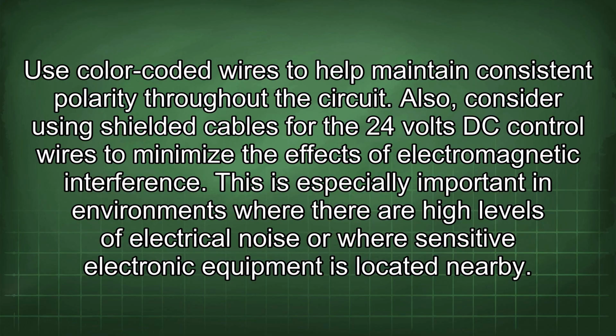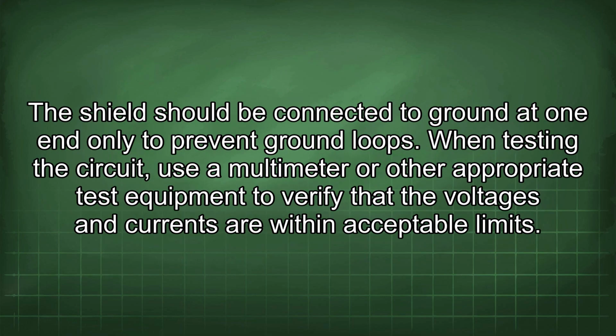Also, consider using shielded cables for the 24 volts DC control wires to minimize the effects of electromagnetic interference. This is especially important in environments where there are high levels of electrical noise or where sensitive electronic equipment is located nearby. The shield should be connected to ground at one end only to prevent ground loops.